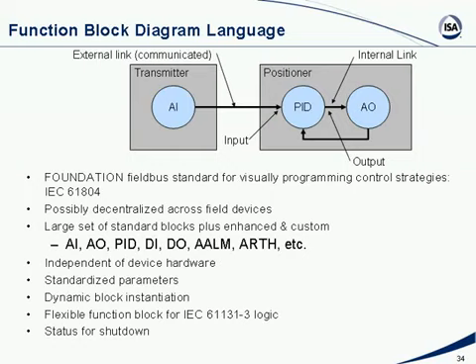So as you can see from this slide, I have built a control loop consisting only of the transmitter and the positioner. There's no centralized controller involved, so it's a completely decentralized control strategy. Now, this works, and it works very well. Most fieldbus installations use this scheme, maybe 80% of all the control loops. Not 100%, but maybe 80% of the loops use this scheme.